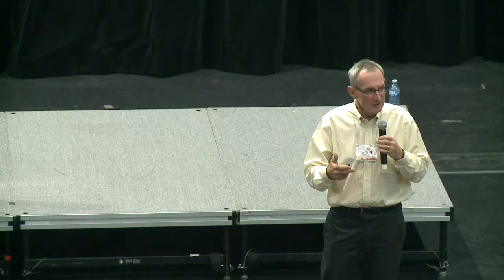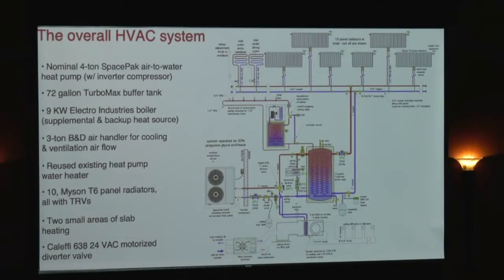So we talked to the manufacturer, and they said, well, we can actually program the ECM motor and give you a speed tap so that you can run this thing at about 150 CFM during ventilation mode, and when you go into cooling mode, you can kick it up to 1,200 CFM. So that's the way we set it up. So the HRV is doing roughly about 120 CFM. It injects it into the return side of the air handler, and then nominal 150 CFM, 24/7, moves it through the building. We also set it up so that in the bathrooms, there are timers, and if you press the timer, it'll kick the HRV into a high-speed mode, so it helps to move moisture out of the bathrooms.